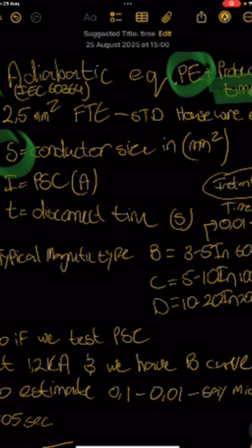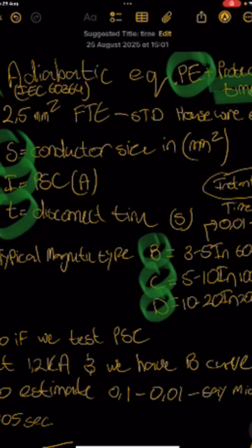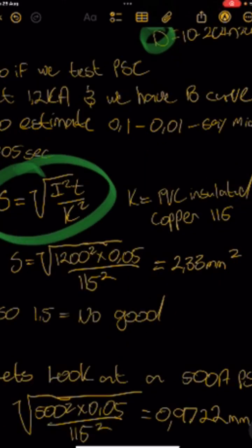S in the calculation is the conductor size in millimeters squared. I is your PSC measured at your control point. T is time taken depending on the spec of your circuit breaker. The B-spec will trip between three to five times its rated current — it'll trip instantaneously, meaning it'll trip from 0.01 seconds to 0.1 seconds. That'll be the trip time in the actual equation.